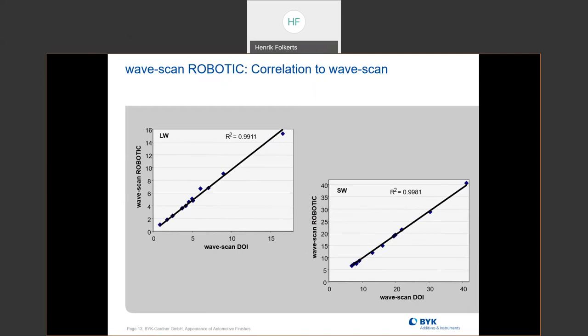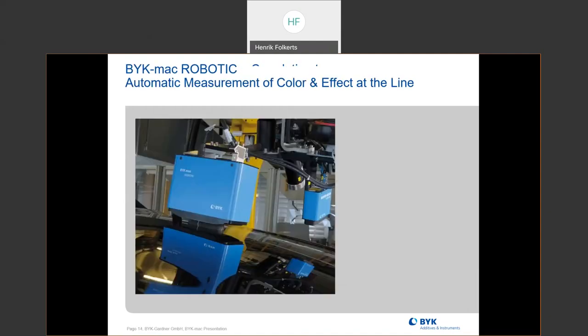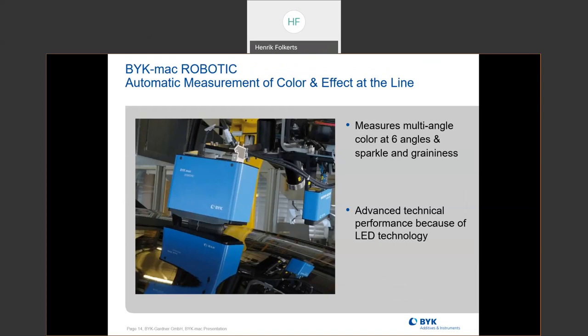This is a comparison of the long wave and the short wave, which a lot of OEMs still use for their appearance data — that also correlates very well. And then we come to the BYK-mac. The BYK-mac gives you the six angles of measurement, the sparkle, and the graininess, which is what is currently in our handheld. It has really good performance because of the LED technology — it's very temperature and humidity stable, so even if you have the BYK-mac out in your plant on a line somewhere, the temperature and humidity is not going to affect your measurement.